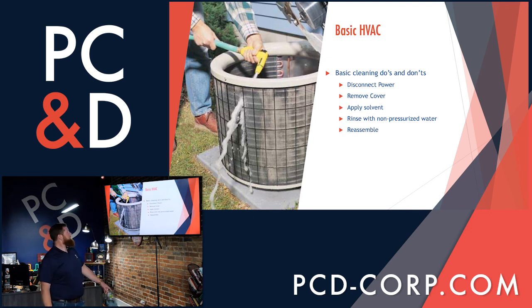After that, we're going to take off the cover of the condenser, in which case a lot of times that brings the fan along with it. So always remove the screws all the way around and bring the wires closest to the motor so as not to pull the wires out of the contactor, which is further into the unit. After that, we're going to apply our solvent in and around the condenser area of all the coils. And once that's soaked in and let sit for a little while, it will begin to foam and you'll actually see debris falling out of the solvent.